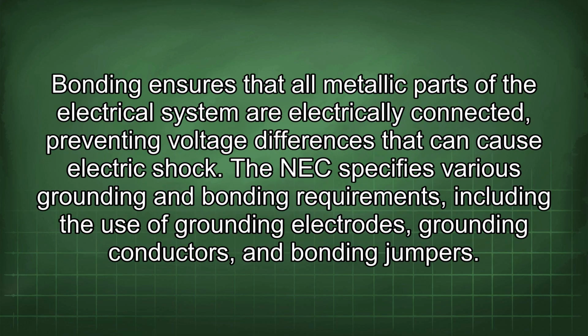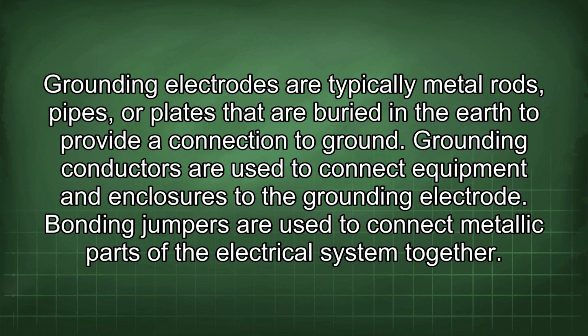Bonding ensures that all metallic parts of the electrical system are electrically connected, preventing voltage differences that can cause electric shock. The NEC specifies various grounding and bonding requirements, including the use of grounding electrodes, grounding conductors, and bonding jumpers. Grounding electrodes are typically metal rods, pipes, or plates that are buried in the earth to provide a connection to ground. Grounding conductors are used to connect equipment and enclosures to the grounding electrode. Bonding jumpers are used to connect metallic parts of the electrical system together.